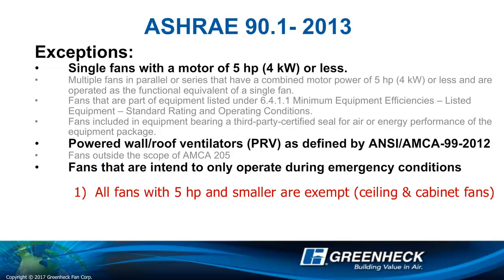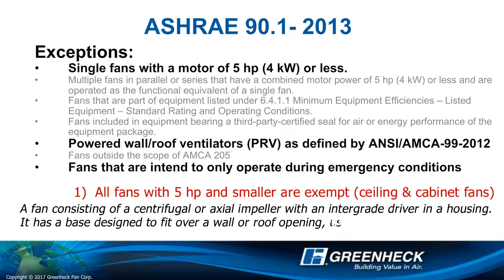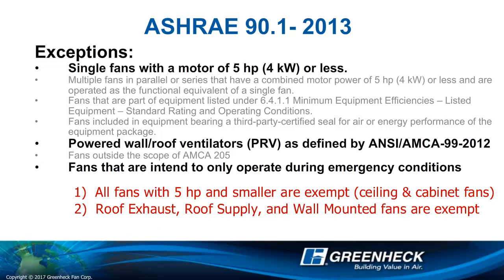Second, all powered wall and roof ventilators, also known as PRVs. The AMCA definition of power roof ventilators is a fan consisting of a centrifugal or axial impeller with an integral driver in a housing. It has a base designed to fit over a wall or roof opening, usually by means of a curb. This means all of Greenheck's roof exhaust, roof supply, and wall mounted fans are exempt.